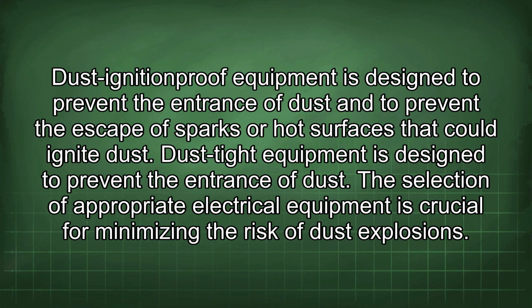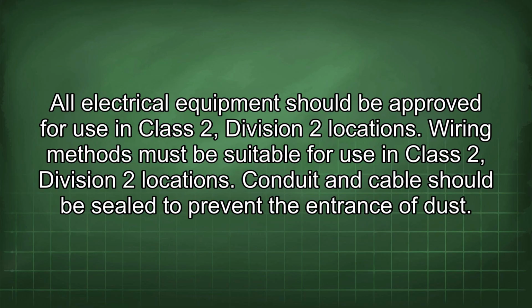The selection of appropriate electrical equipment is crucial for minimizing the risk of dust explosions. All electrical equipment should be approved for use in Class 2, Division 2 locations. Wiring methods must be suitable for use in Class 2, Division 2 locations. Conduit and cable should be sealed to prevent the entrance of dust.